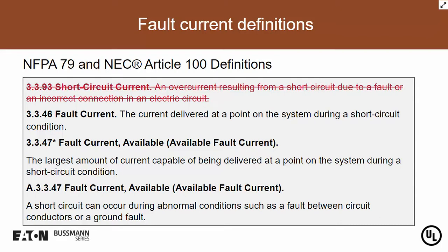So depending on where you're at in a particular circuit, the fault current could vary considerably. For example, if you are downstream from the source of supply, you have considerable impedance between the source of supply and that point where you're at, and so the fault current can be reduced considerably, whereas the available fault current would be the current that's at the point where the supply is connected to the equipment, and that's generally the point at which you're most concerned, because there you can determine if the equipment has an adequate short circuit current rating. And then we added some annex material indicating that short circuit can occur during abnormal conditions, such as a fault between circuit conductors or a ground fault.